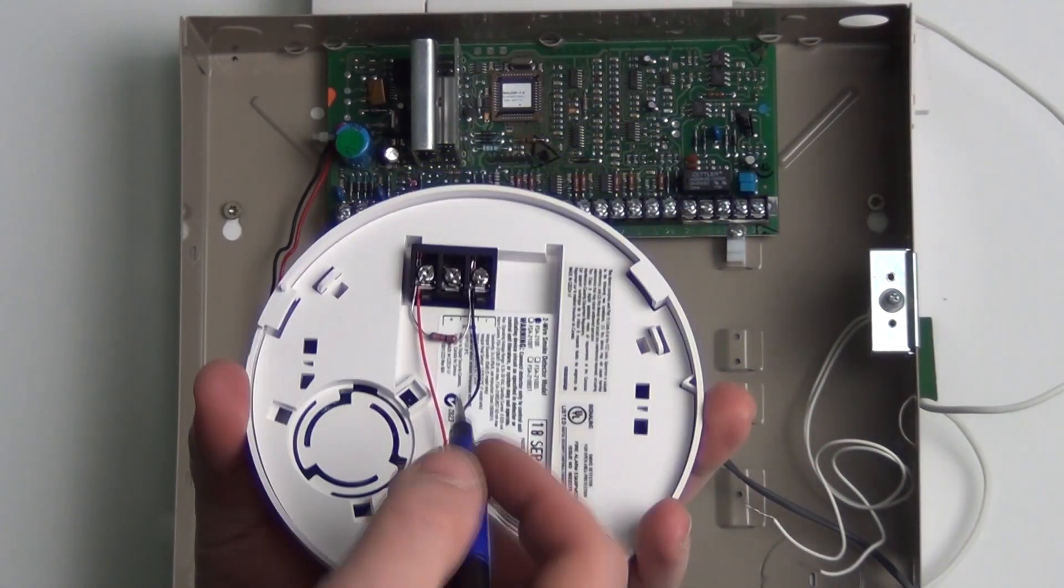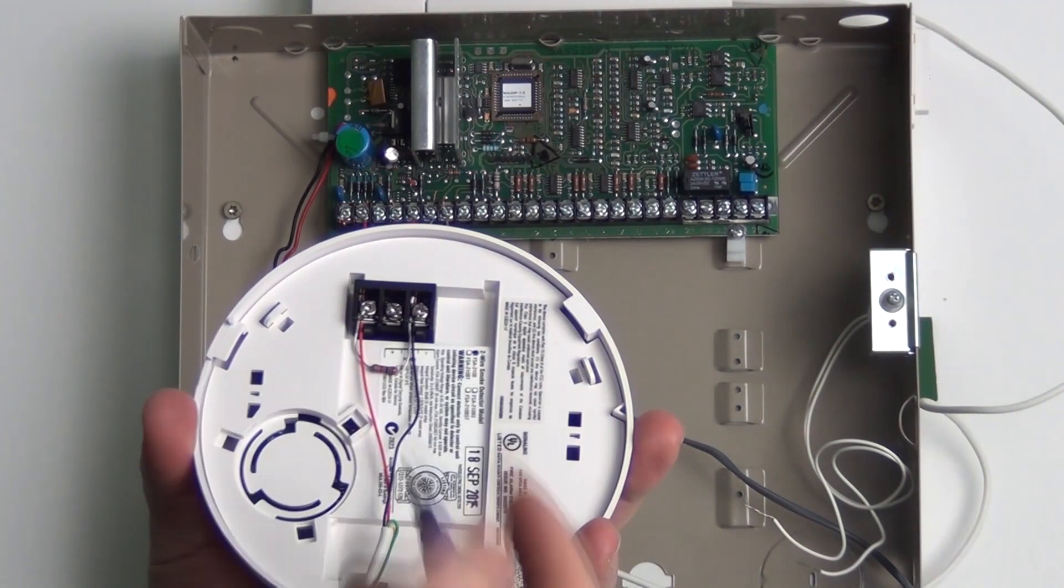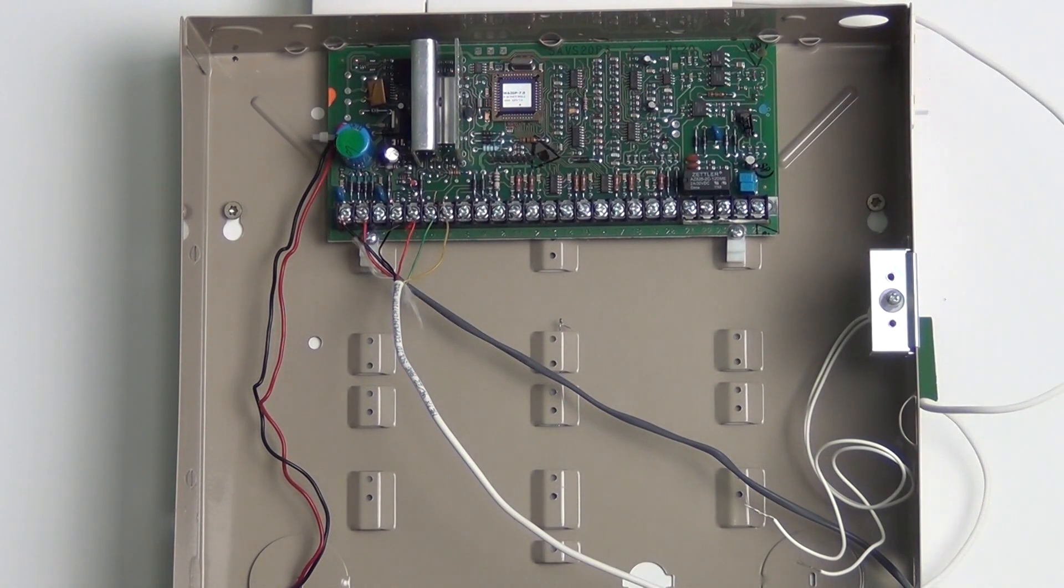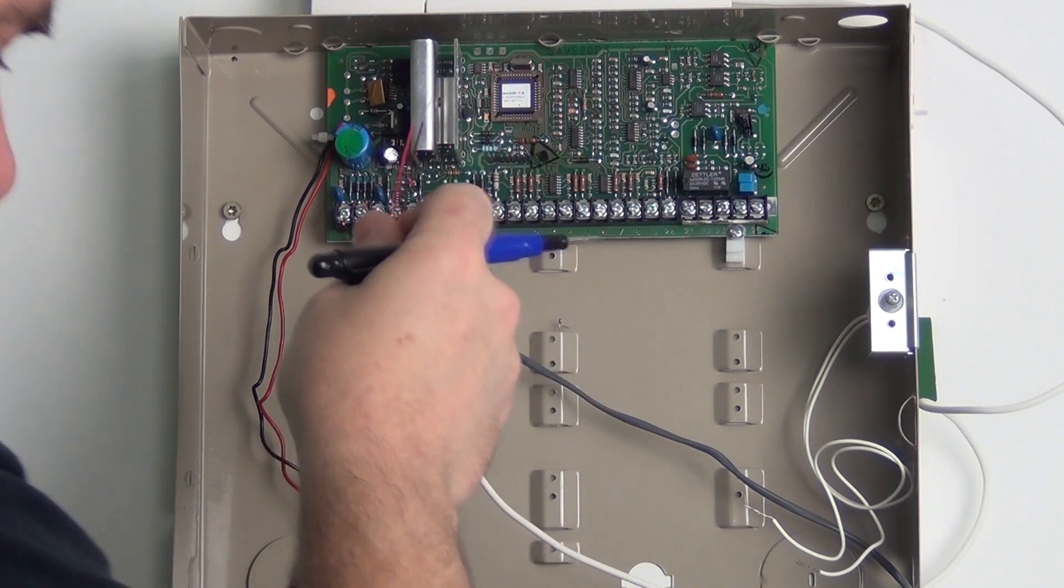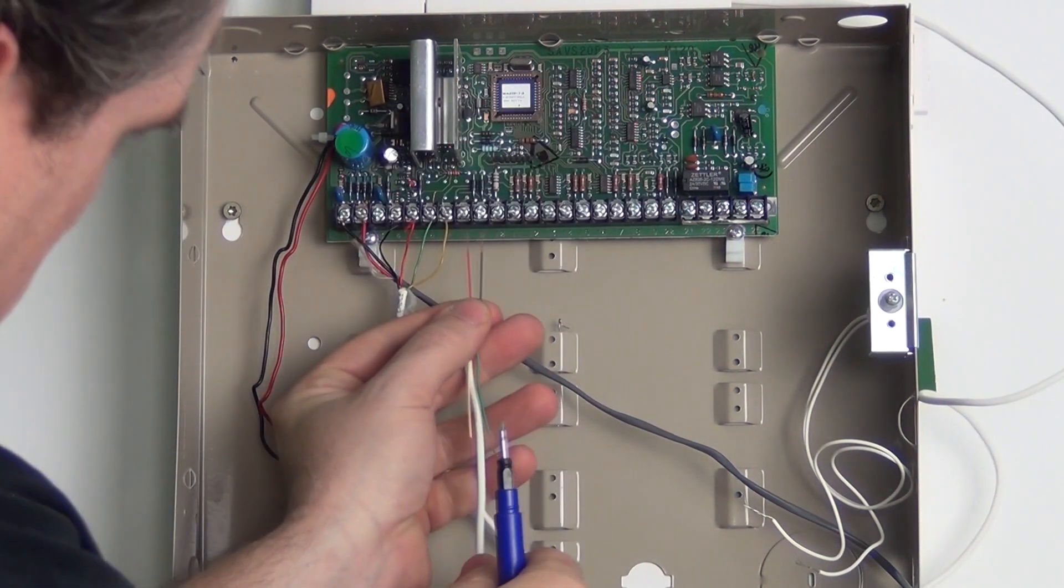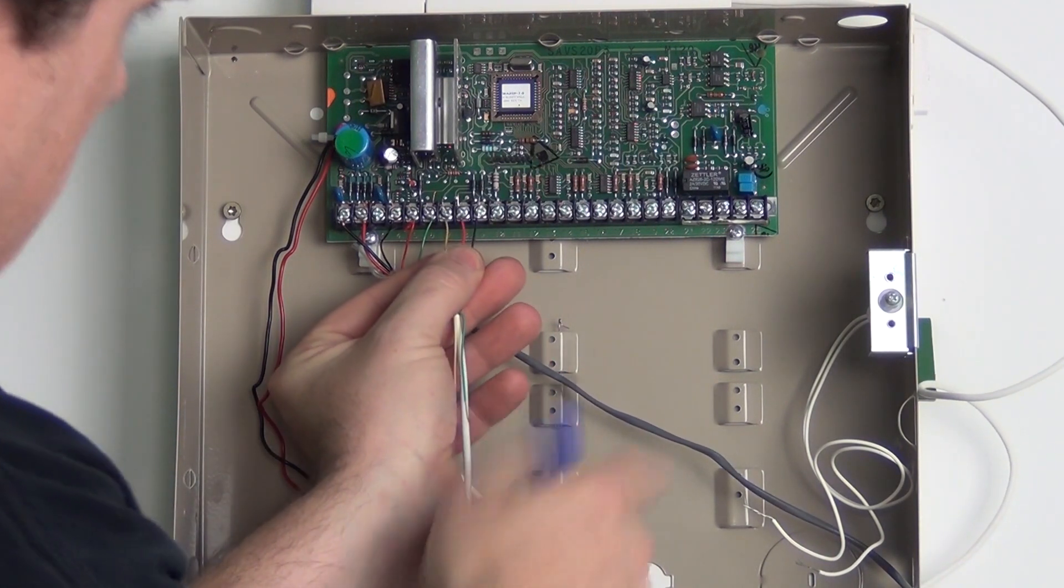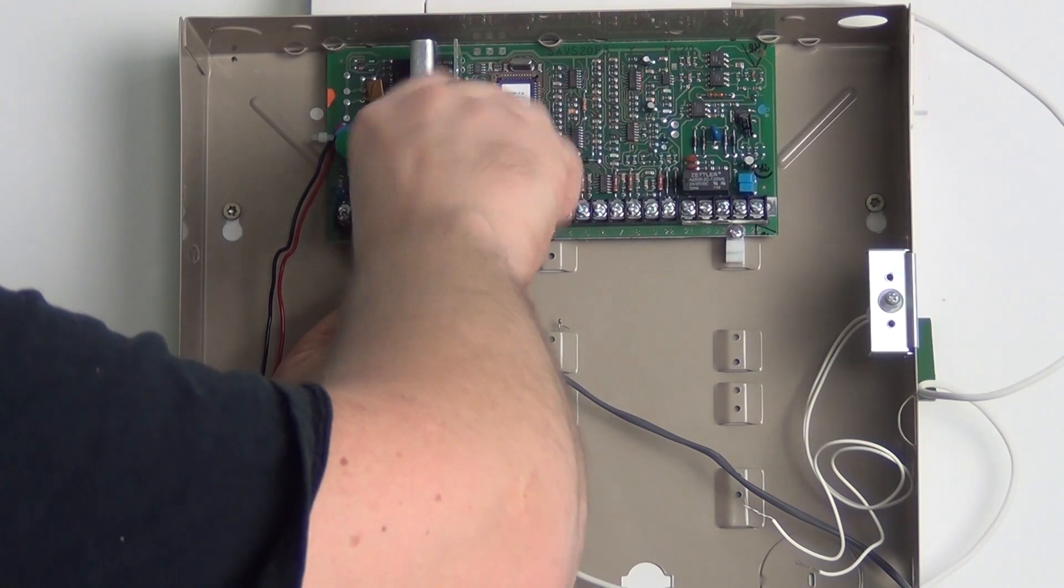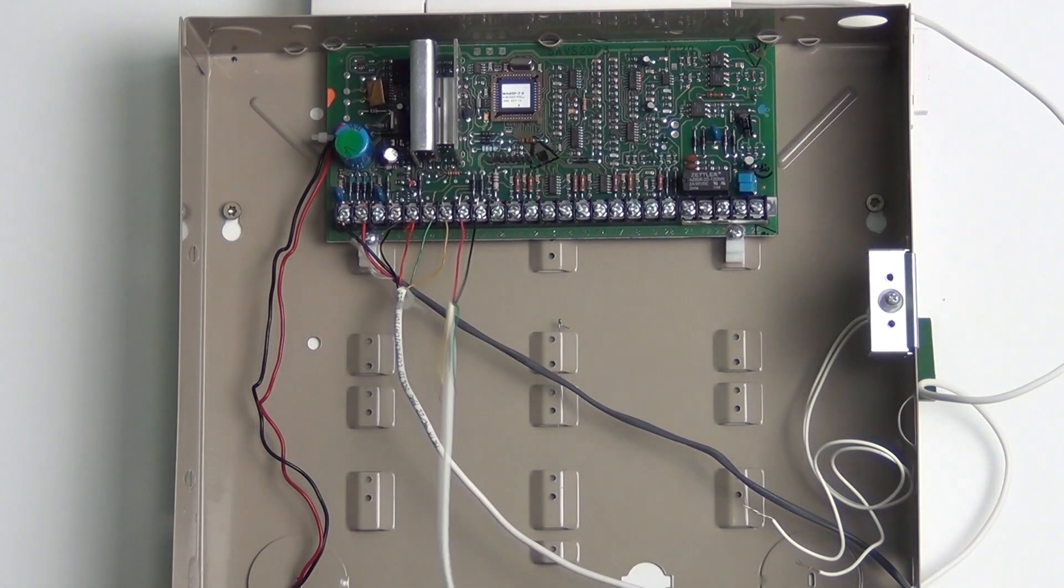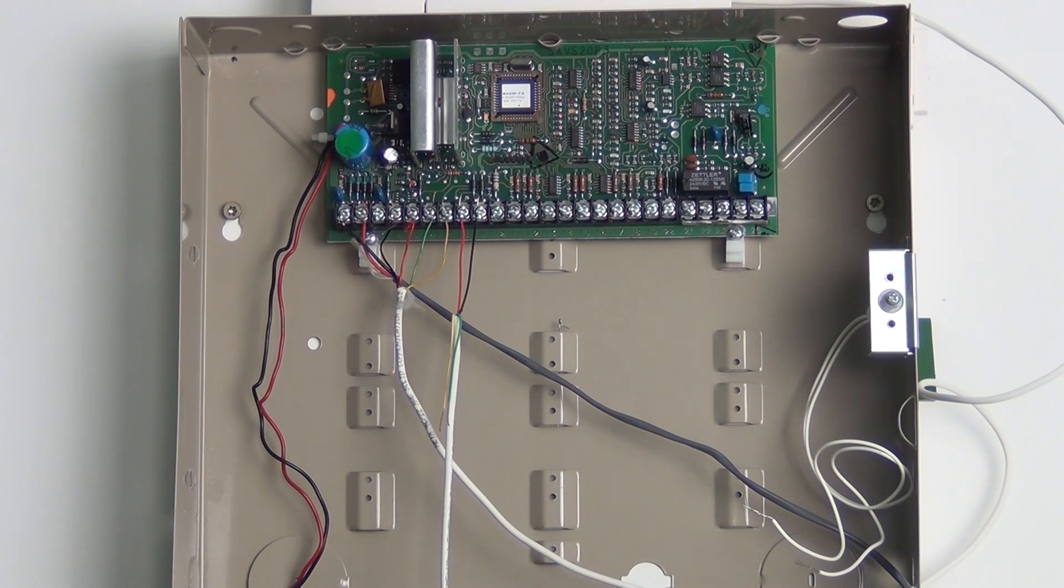I've taken the red wire to the positive, the first positive here, and taken the negative to this last terminal which is the negative. Then I've ran a resistor in parallel between these two. I'm going to take the other end of these wires over to terminals 8 and 9, which is zone 1 on the Honeywell Vista system. I'll stick one wire under 8 and the other wire under 9, then tighten those screws down. There you have it—two-wire smoke wired into the panel on zone 1. Normally open devices such as smokes and heats will be ran in parallel, as opposed to other devices that are normally closed which you will run in series.